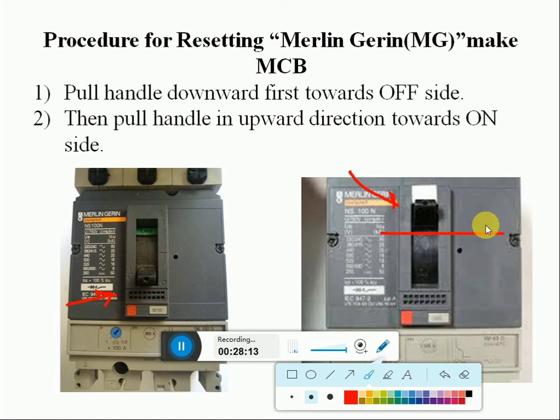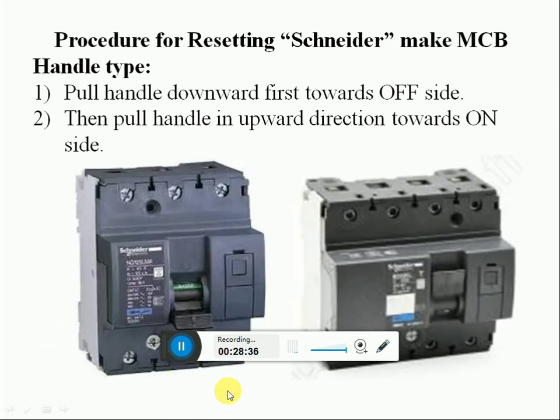Any MCB trip, pull the handle to downwards first, then move into the off position. Then only this MCB will reset. 3 position MCB. On, off. This is also 3 position MCB. On, trip, off. If it is trip, we have to bring to the off position, then we have to move to the on position.